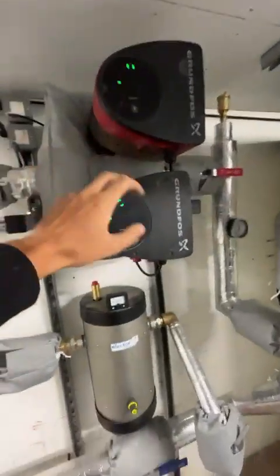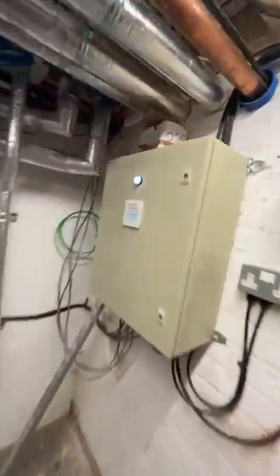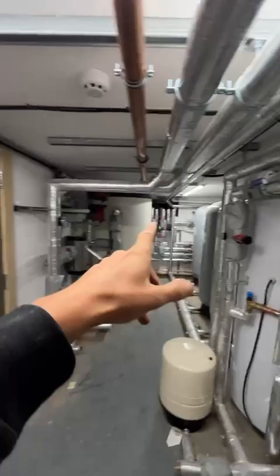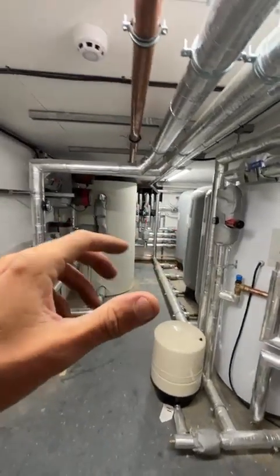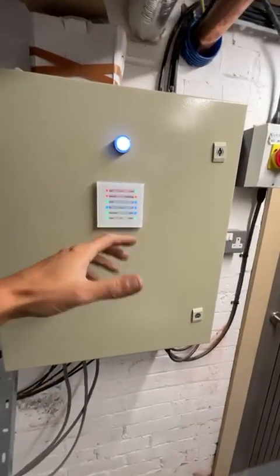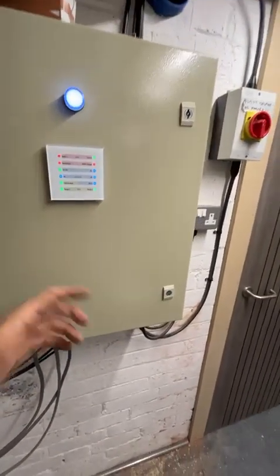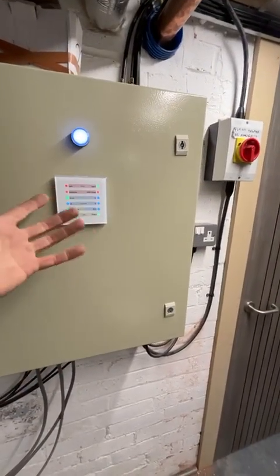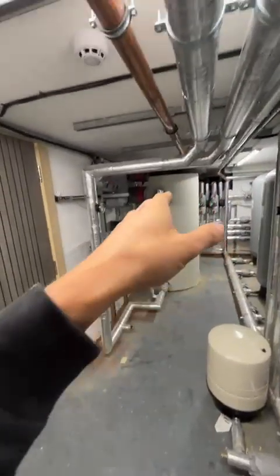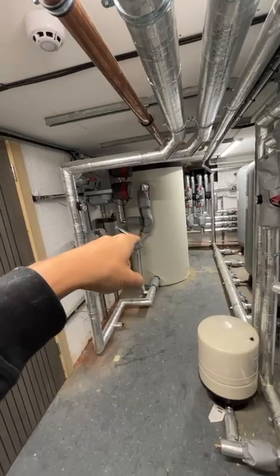Pump 1, pump 2 - at times we can pull pump 1 on or pump 2 on. What we can also do through this, because we're running Modbus back to the Heliotherms, is take it higher, tell it we want it when there's low electric use, low cost electric tariff, and take that buffer temperature up - that's what that fixed flow is for there.